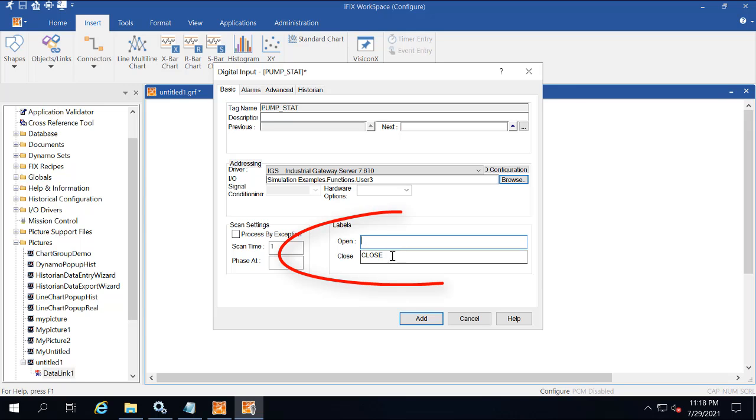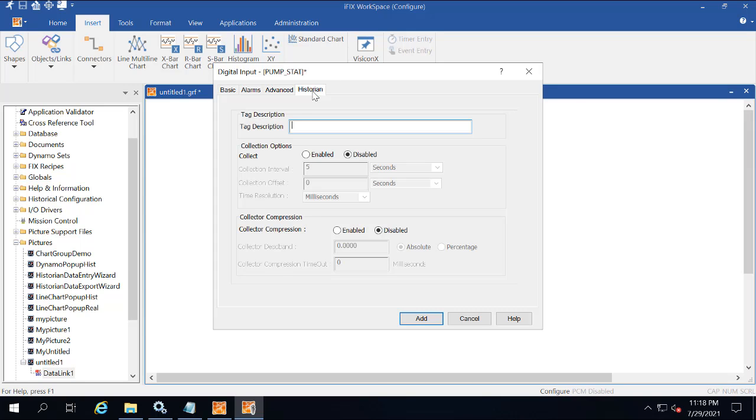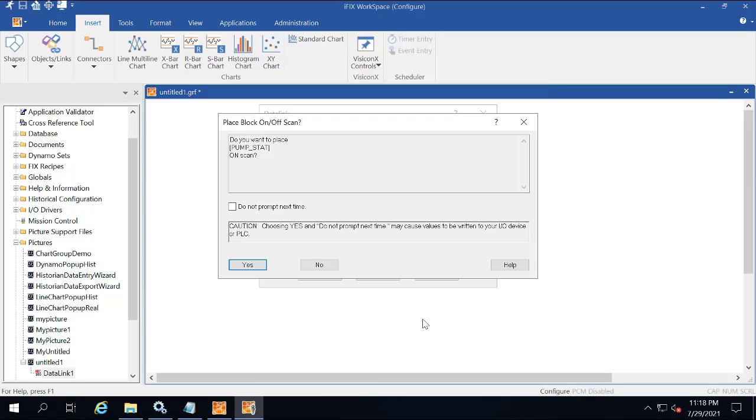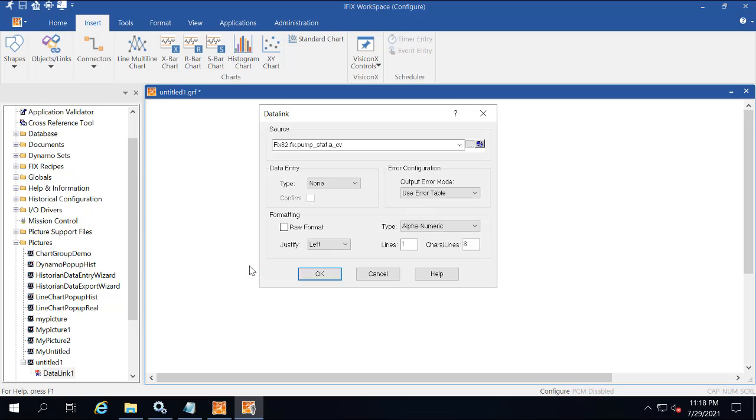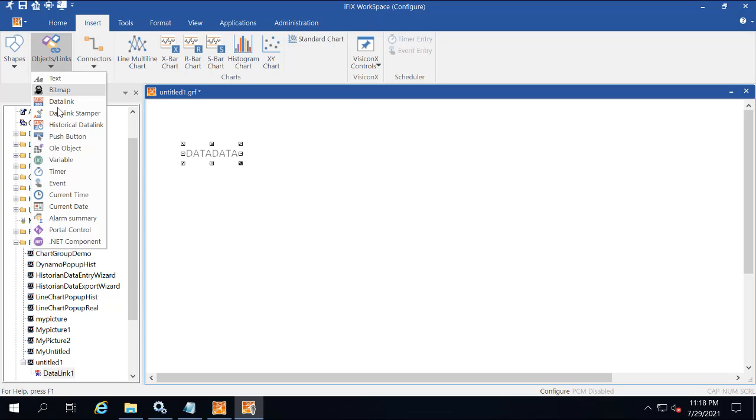In the labels area, change the open and closed labels to stopped and running. Now click the historian tab. In the collection options area, click Enabled, and then Add. A message should appear about putting the blocks on scan, so just click Yes. Now click where you want the data link to appear in the picture.